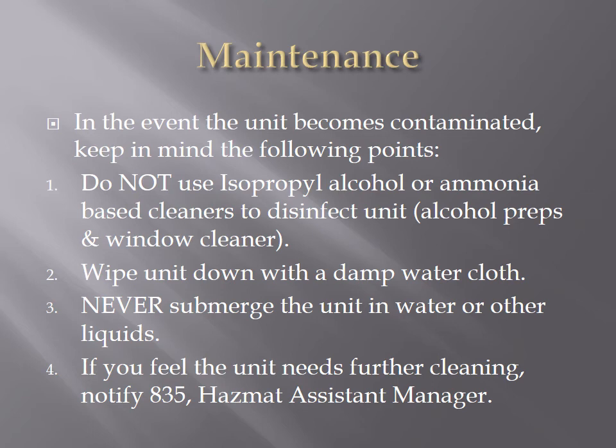Let's talk about maintenance of this monitor. Maintenance is relatively low for this unit, but there are some things we want to discuss. In the event that the unit becomes contaminated, for example, with soot from a structure fire or anything else, don't use isopropyl alcohol, alcohol preps, or ammonia-based cleaners to disinfect this unit. The vapors given off by the alcohol or the ammonia can harm or damage the monitor itself. Ammonia-based cleaners would include some kind of window cleaner. Again, anything that contains ammonia.